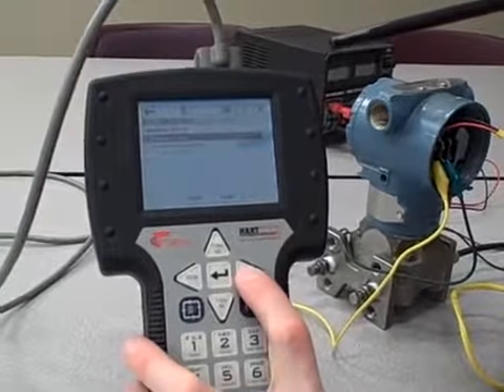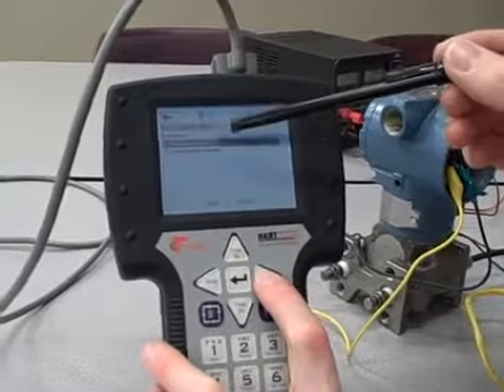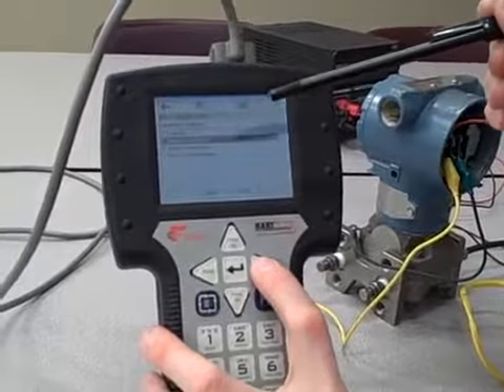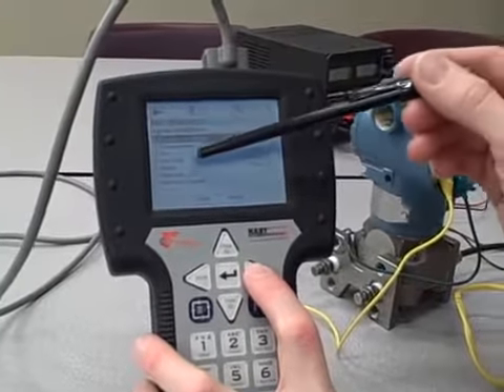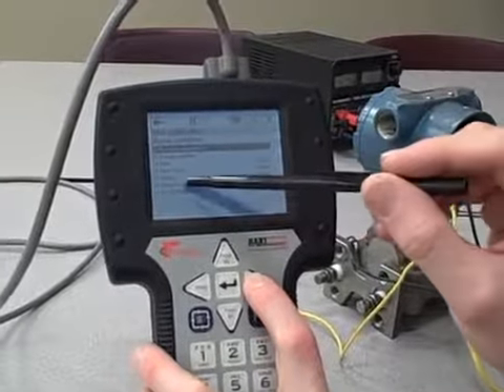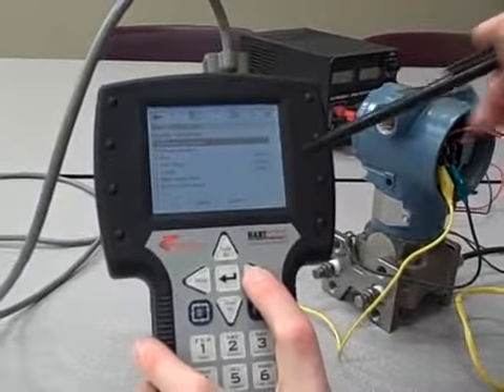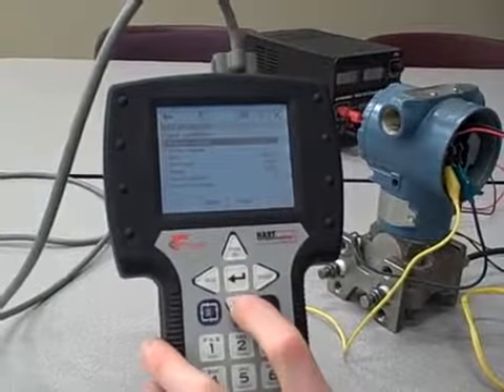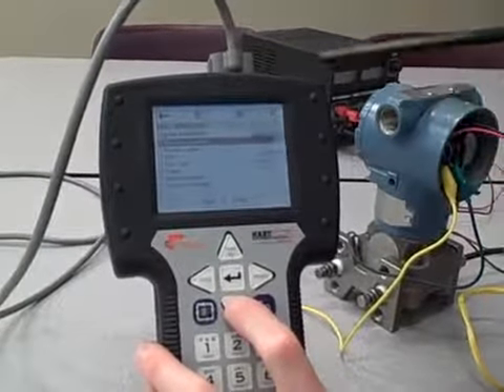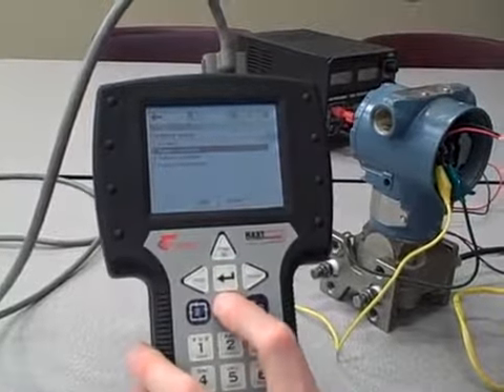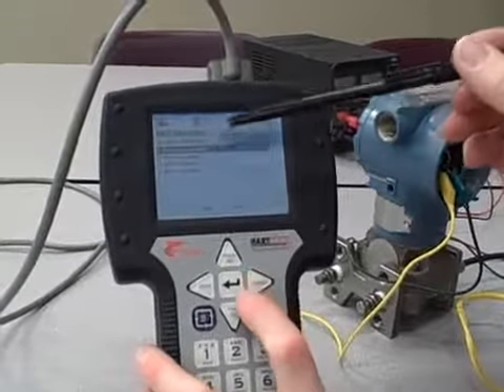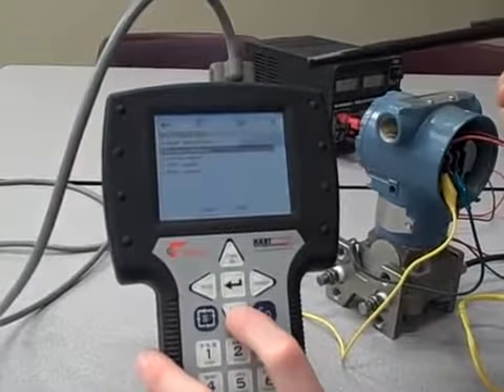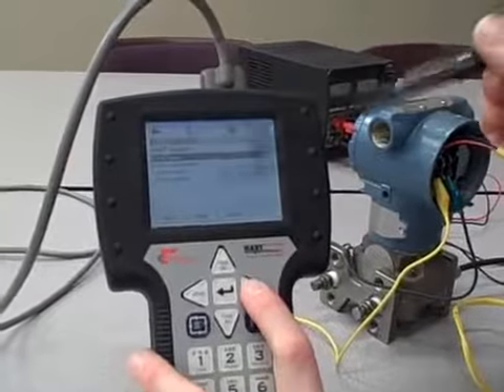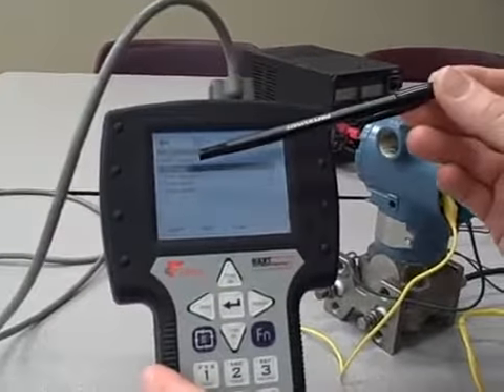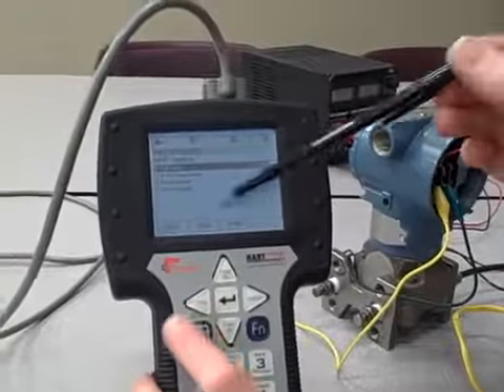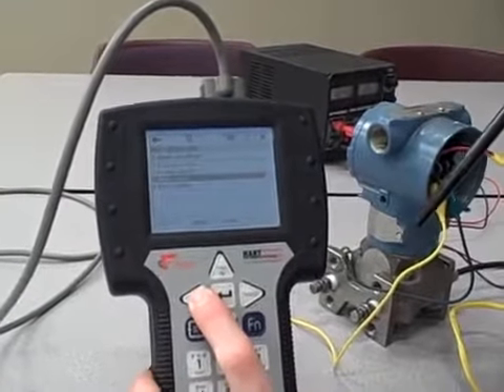We can go into sensors, in which case we can configure things regarding the pressure and temperature sensor. Signal conditioning. Once again, this is a transfer function, linear versus square root. Sensor temperature unit, that's the ambient temperature sensing unit in the transmitter. We can set that for degrees Celsius or Fahrenheit. Alarm saturation levels, damping, range values, etc. We can also go into output condition and configure some things regarding the analog output and the HART output, for example, what variables are output by the HART protocol, the burst mode, for example, and poll address in case it was a multi-drop transmitter, all kinds of things here.